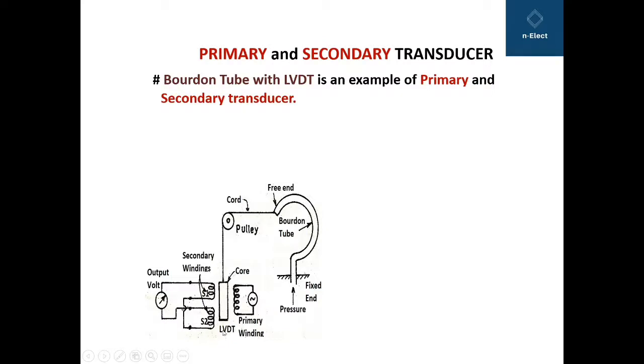The 'linear variable' part refers to the fact that you can vary the output voltage across the secondaries with the movement of the core in a linear way. Since the two secondary windings are connected in series opposition, you get the differential voltage at the output — that is why it is called differential. And since the arrangement is like a transformer, it is called a transformer. So in short, it is Linear Variable Differential Transformer.